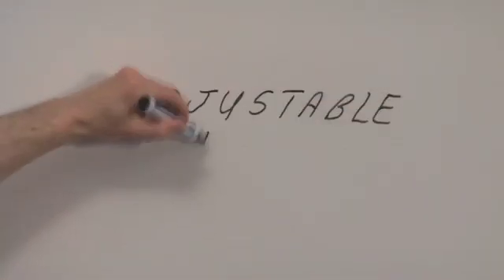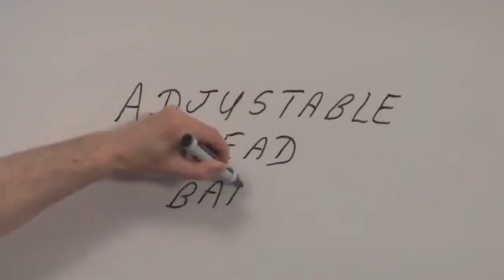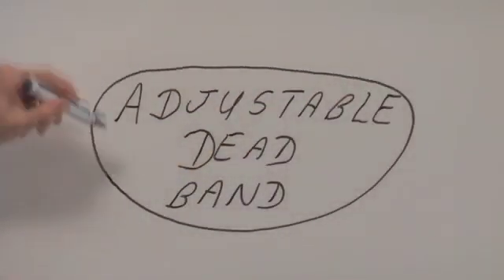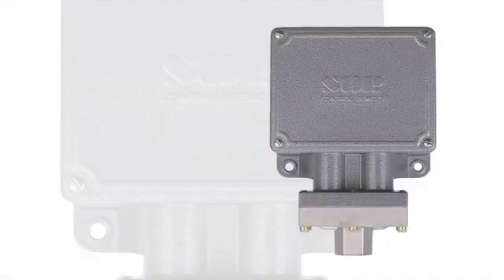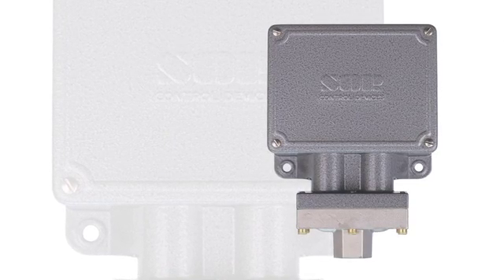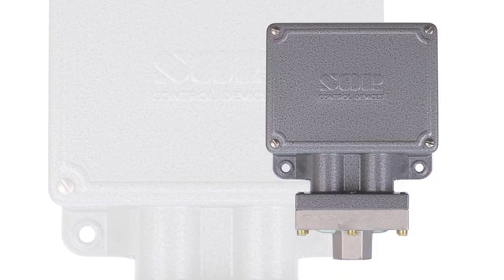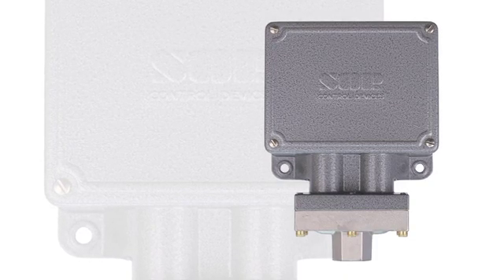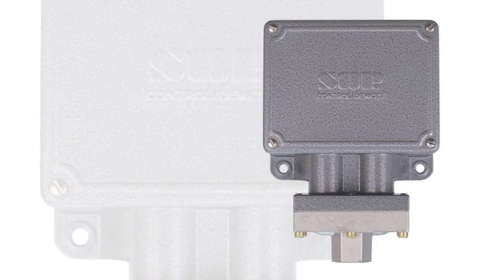At first glance, it may seem that the 805QS offers adjustable deadband functionality. That is not the case. You would not use an 805QS to control an air compressor. Instead, you should use an SOR mechanical pressure switch with an adjustable deadband.